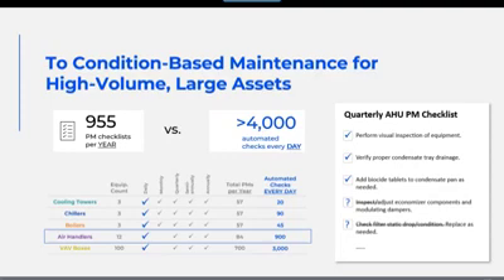Scheduled PM on a packaged rooftop is, let's just say, traditionally done on a quarterly basis and involves items like, hey, we're gonna change the filters, we're gonna calibrate sensors, we're gonna check out sequence of operations and just walk the unit through its normal operation. What condition-based maintenance allows for is for the analytics tool, the FDD, to actually replace items on the actual checklist, taking a more data-driven approach to the service.